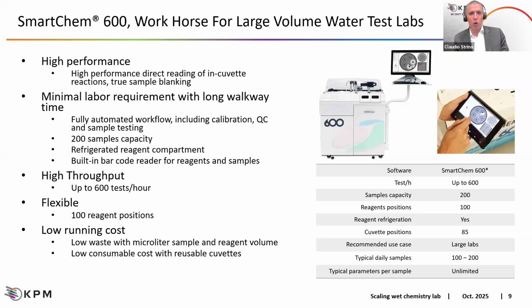Minimal labor requirement, thanks to the long walk-away capability, because we have a fully automated workflow, including preparation and run of the calibration, QC, and samples, up to 200 samples on board. We have a refrigerated compartment for reagents, so the instrument is able to preserve reagents during on-board time. And thanks to the built-in barcode for samples and reagents, we can fully automate the process. What does it mean? That we are no longer prone to any human error in positioning the liquids on board, because we can place the reagents as we want, we can place the samples as we want, with positive recognition by barcode readers, and importing the working routine from LIMS. So everything will be performed without any issue.